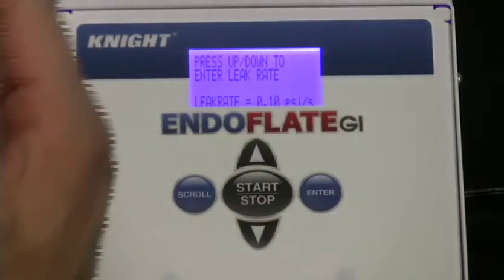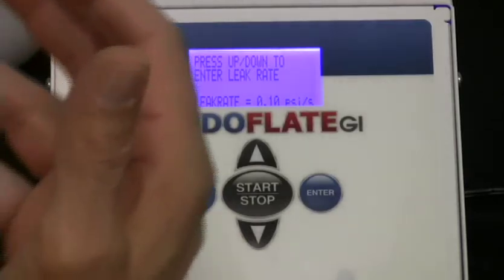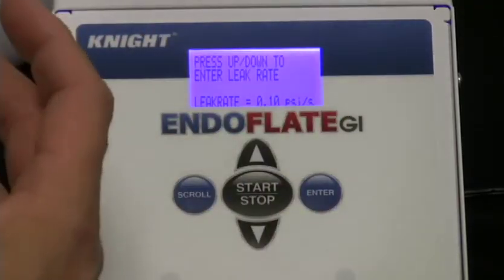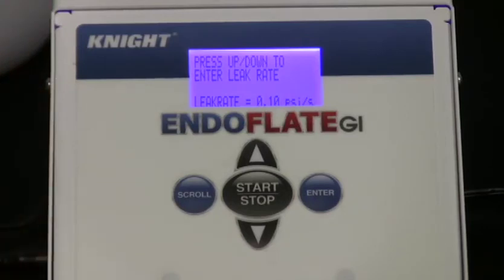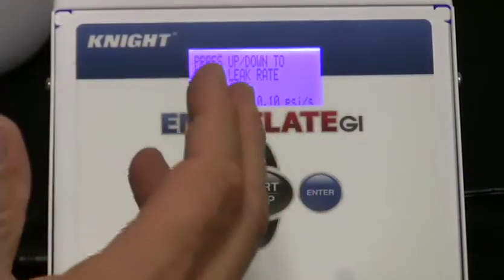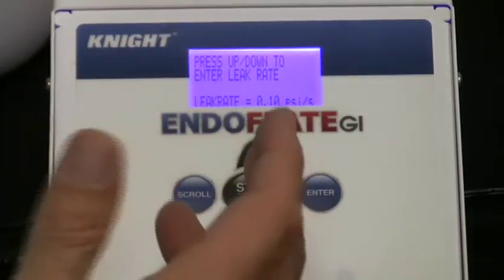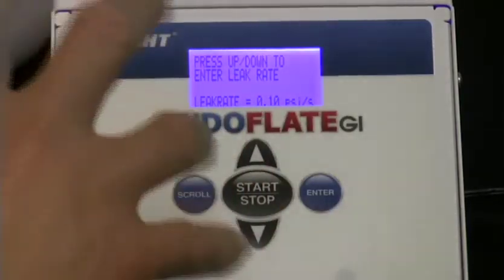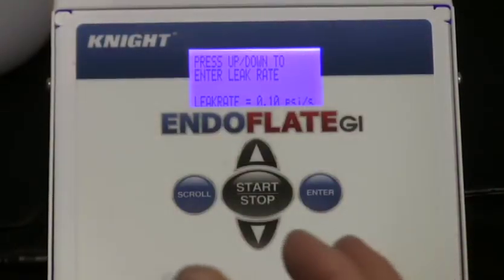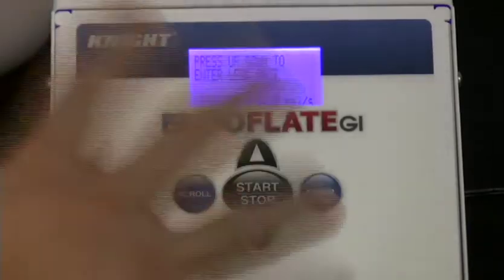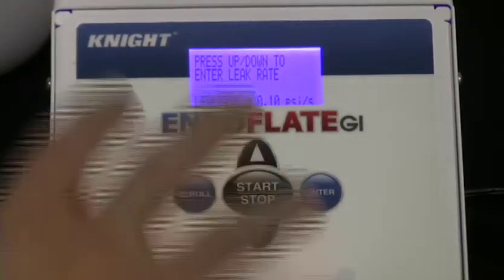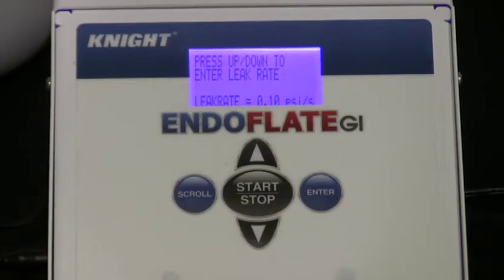A leak is a leak if it allows air into the liner of the scope. We all know there's a lot of sensitive equipment within the liner and the outside covering of that endoscope, so it's important that we keep the moisture out. So we're going to be able to detect a very small leak at that setting, and our air pump can more than compensate for a leak that small and completely pressurize the inside bore of the scope and the liner to keep water out if they want to continue to clean and leave the air pump on. So keep that number in your mind. We're going to leave it at 1/10 psi per second.